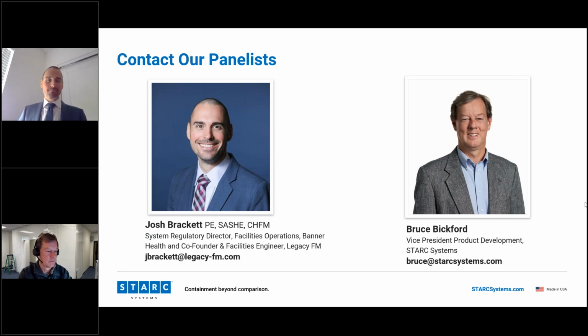Awesome. Josh, does NFPA 241 require you to relocate sprinklers when the ceiling tiles have been removed as part of the construction? Will sprinklers be able to collect enough heat to activate if the ceiling tiles have been removed? You have to bring the sprinkler system up to NFPA 13 requirements, which is where we were talking about. It has to be within so many inches of the deck or the beams or pockets of those structural members. So it does require that you move the sprinkler heads up to the deck.